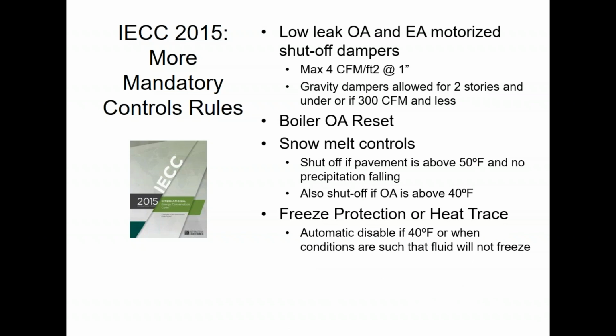your snow melt. If you have freeze protection systems, right, for like piping and stuff like that, like heat trace tape wrapped around piping, those cannot be running wild. They have to be controlled, and they have to be controlled to a specific set point of 40 degrees for normal fluids like water.